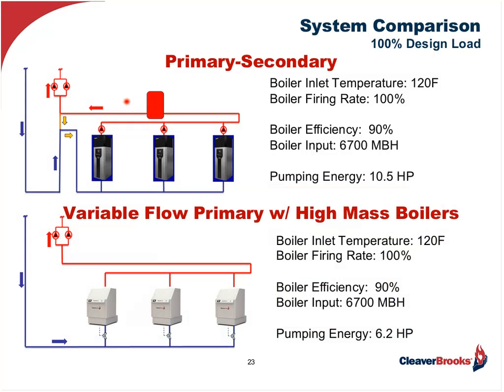Before I do that, one other thing I want to point out. There is one difference. You look at the pumping energy. Because you have those 3 primary pumps, it's about 4 horsepower greater using primary-secondary versus variable flow pumping. So you will be saving energy, just not boiler energy at full load.